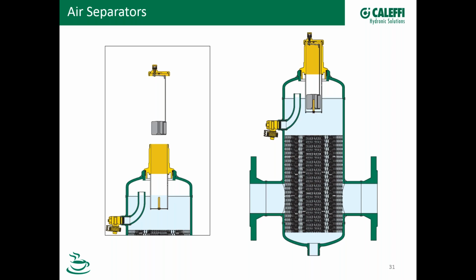If you do need to clean it for some reason, if you have really bad water, the whole thing comes apart. So you can get in there and service it. And this thing right here on the side is called a side drain vent. What that is for is you can open that to release large amounts of air when you're filling the system. So you don't have to wait for the little air vent to purge out the air when you're doing your fill. Just open that valve and let that air come out quickly during the fill.